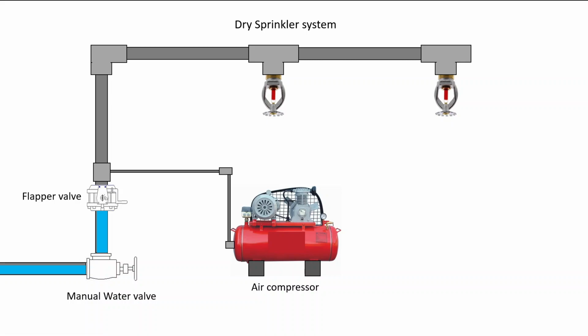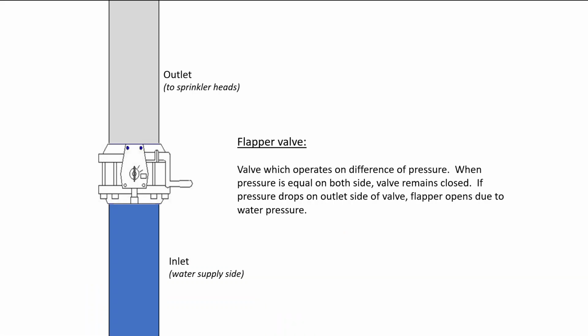In order to operate a dry sprinkler system, we need an air compressor. The air compressor's role is to pressurize this portion of the piping with compressed air. It also has a flapper valve. A flapper valve is paramount in this operation. The valve which operates on difference of pressure is a flapper valve. When pressure is equal on both sides of it, the valve remains closed. If pressure drops on the outlet side, that'd be up here, then the flapper opens due to the water pressure down below.